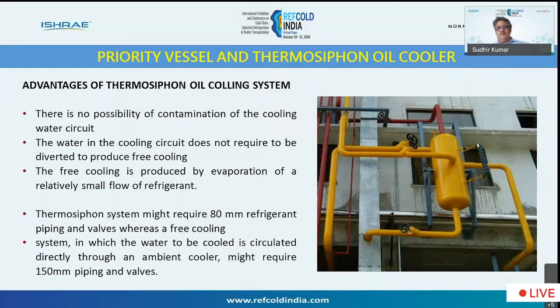So basically, using a thermosiphon oil cooler, you don't need to use any pump. It flows by gravity. Ammonia at 40 degrees cools your oil to 45 degrees. This is one of the better systems which we are now using.